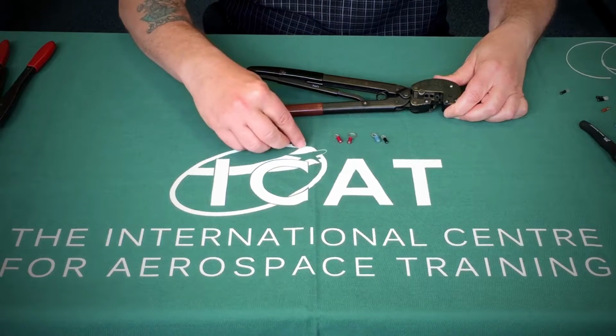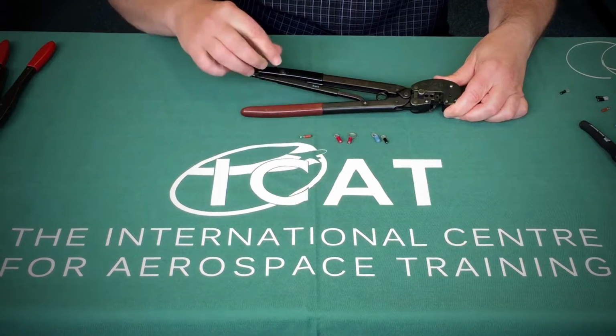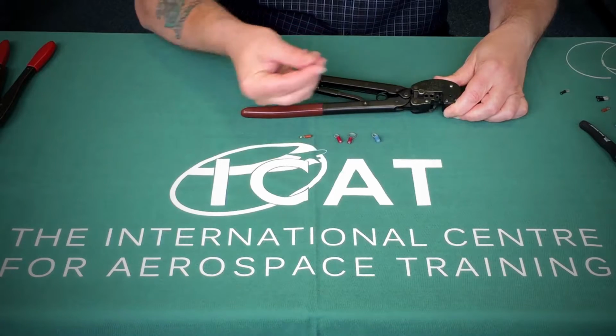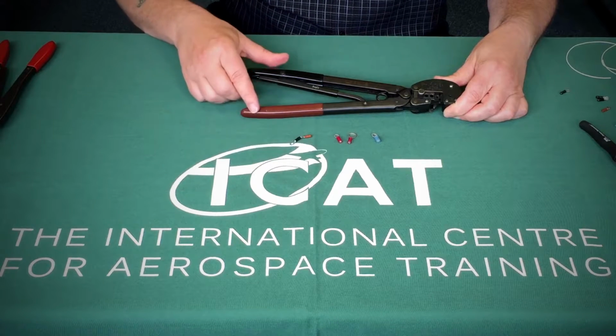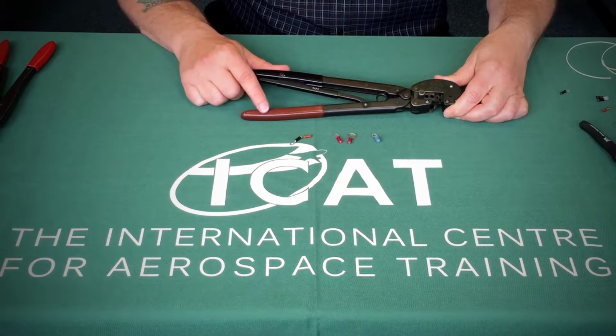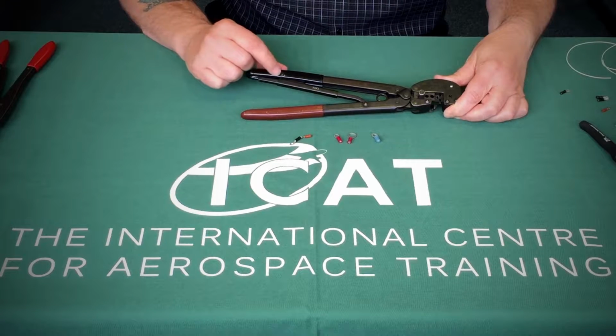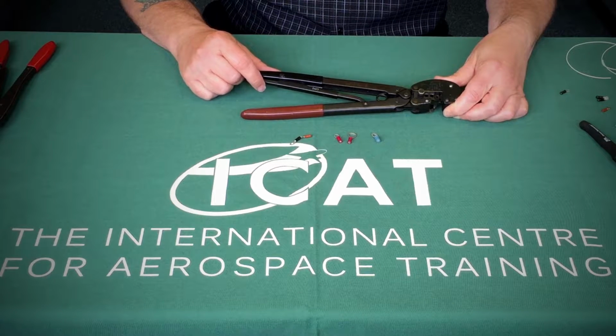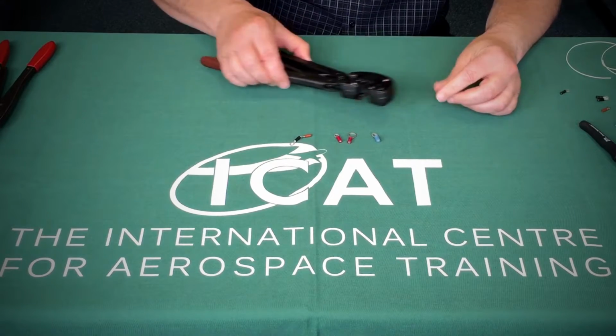So we've got the brown handle, so we can use this tool to use the brown crimp, or the black handle can be used with this type of crimp. The difference in the colour handles is the brown handle is for a high temp crimp and the black handle is for a standard crimp.